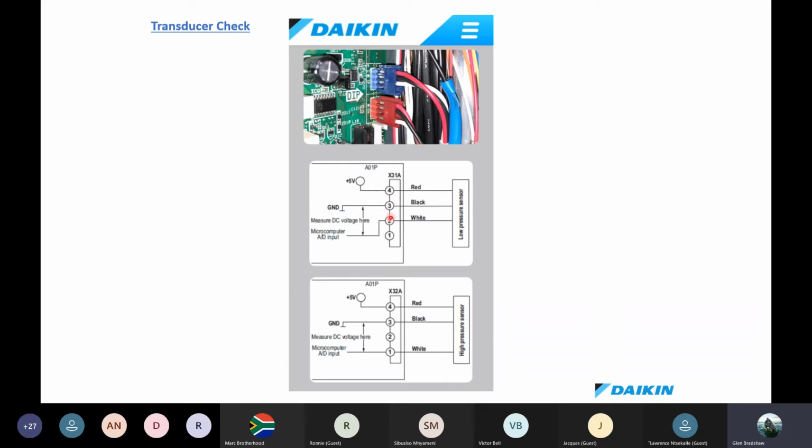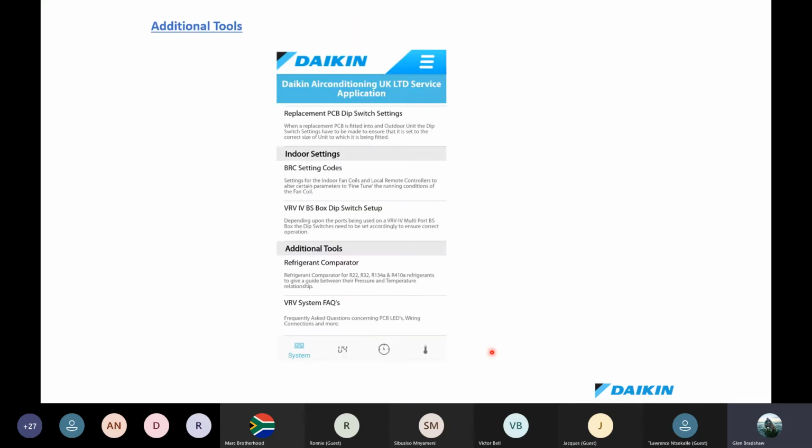But also note that you need to know these plugs because you're going to need to carry out the voltage test. Okay, and you can see here that if you measure between 1 and 3, okay, this is where you're going to get your varying voltage. The power supply onto the device is through 3 and 4. Okay, so there's just a basic diagram, and that's given to you there as well. All right.